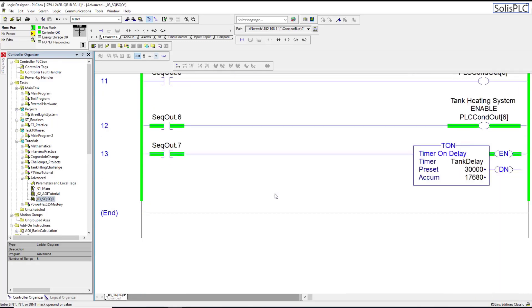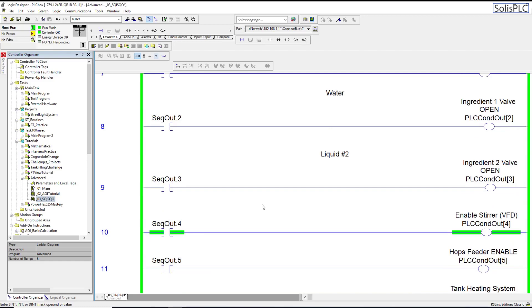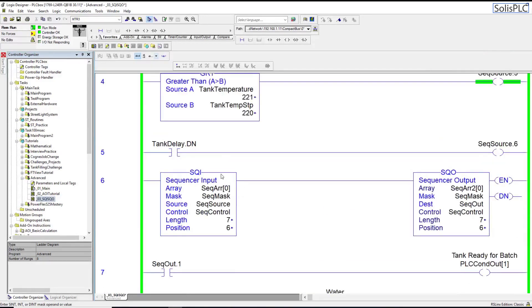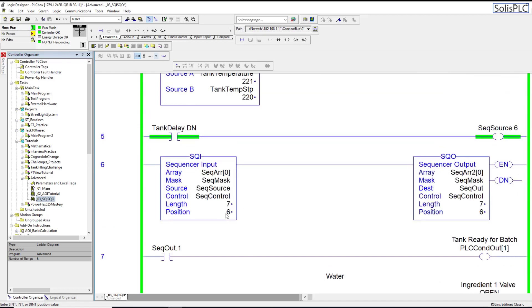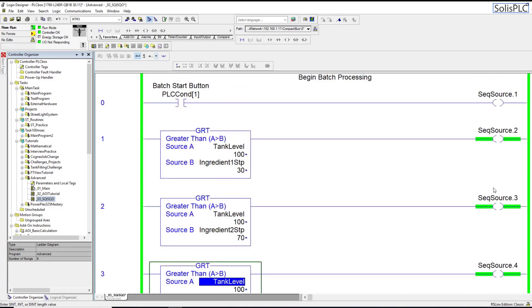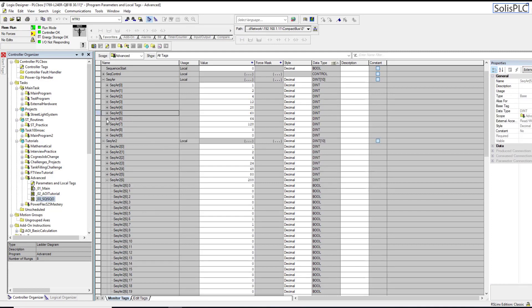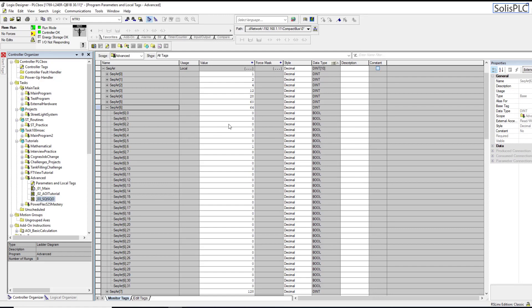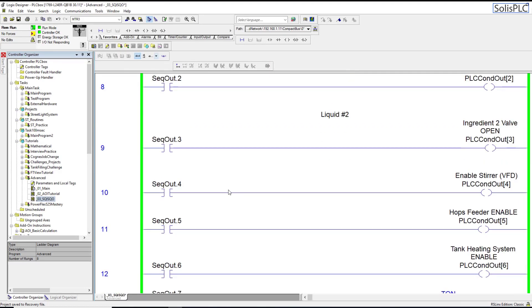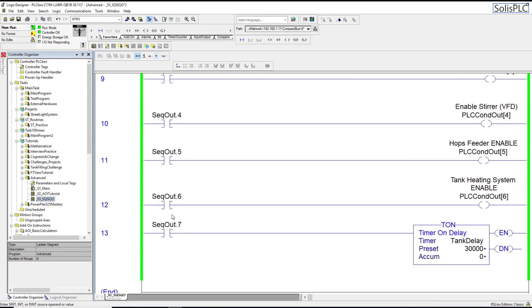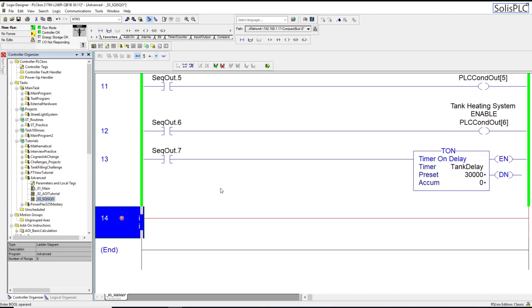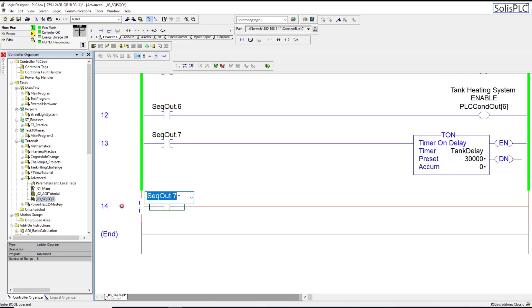We should be able to jump to step number seven once that timer is done, and that timer essentially tells us the tank is ready for discharge. But one thing that prevents us from going to seven is that we now have all these bits set, so we need to look for them as well. Since the temperature is definitely maintained, that's a requirement. Now we are in output number seven - output number seven is going to discharge the tank. The tank is now ready for discharge, we don't have anything else going into the tank, the batch has been completed.